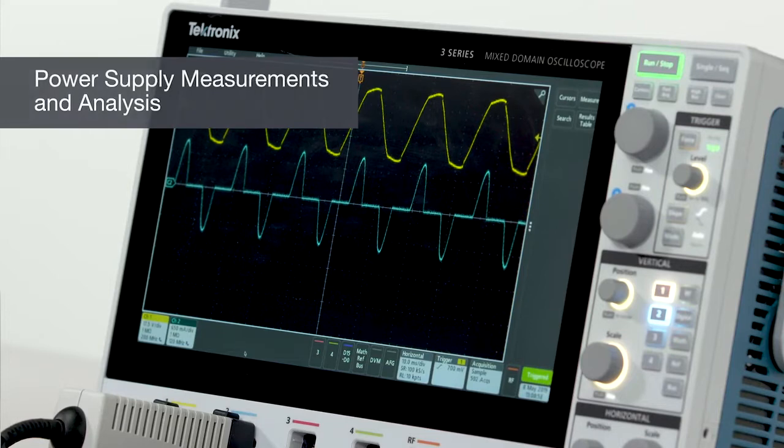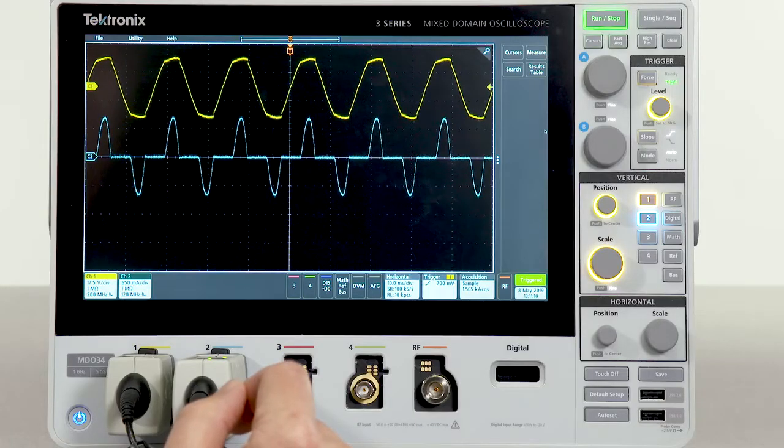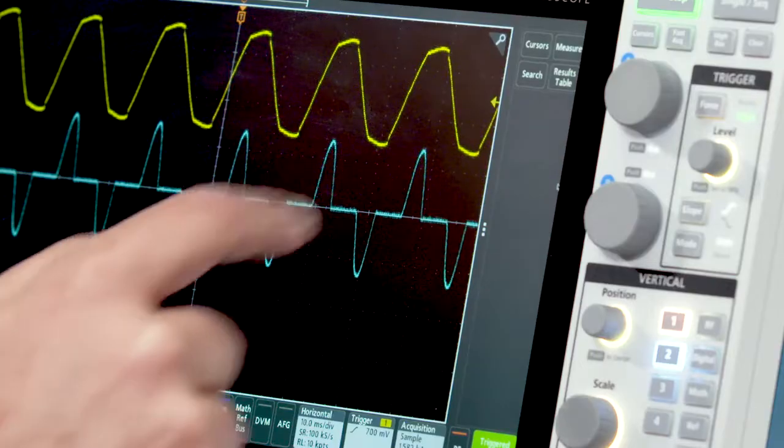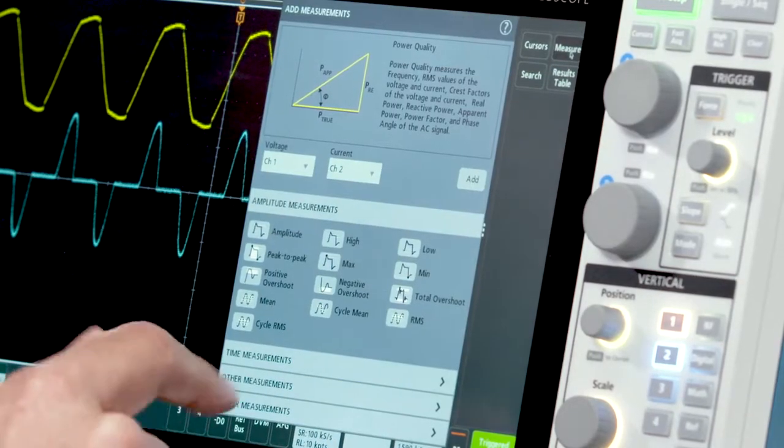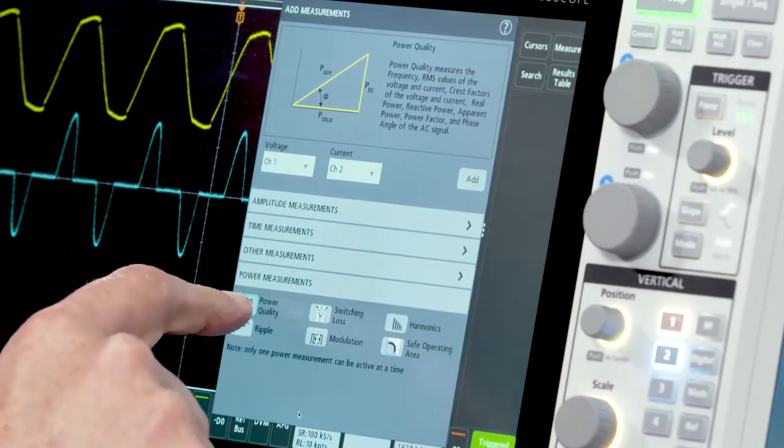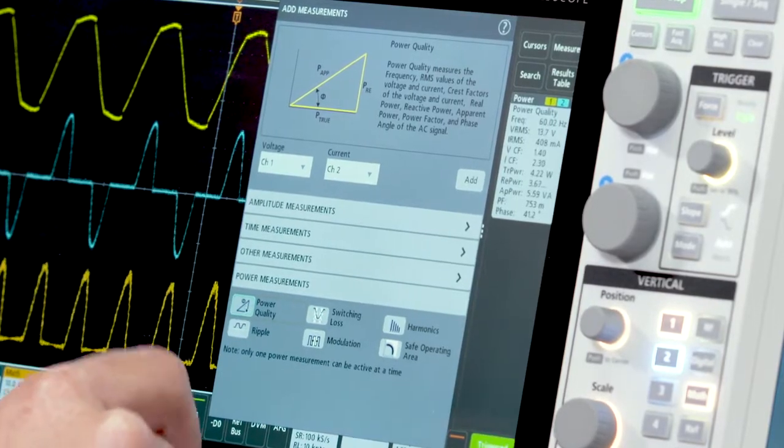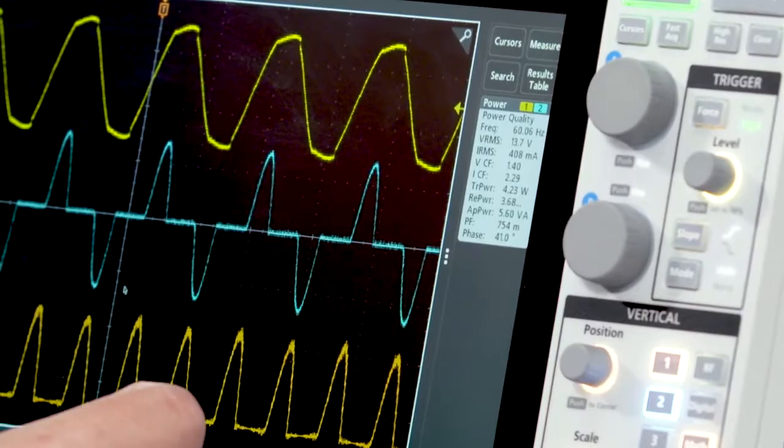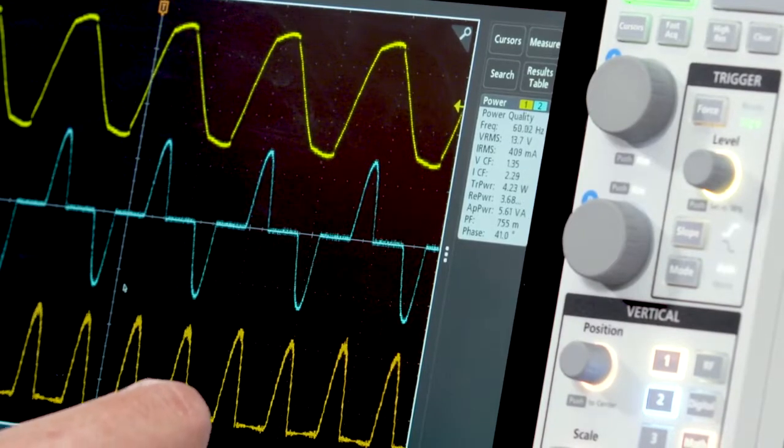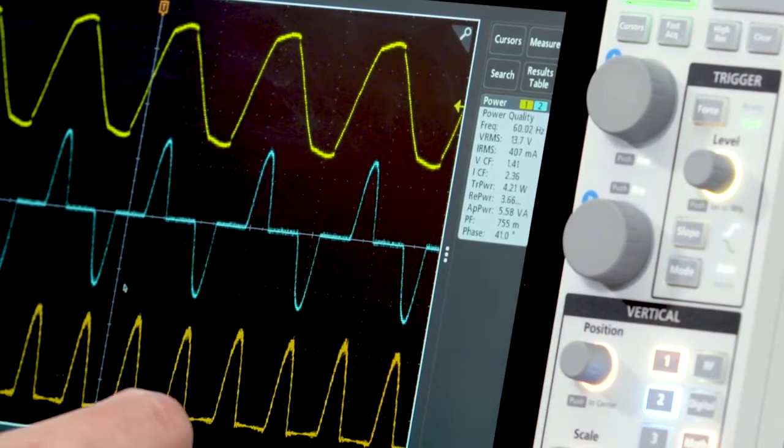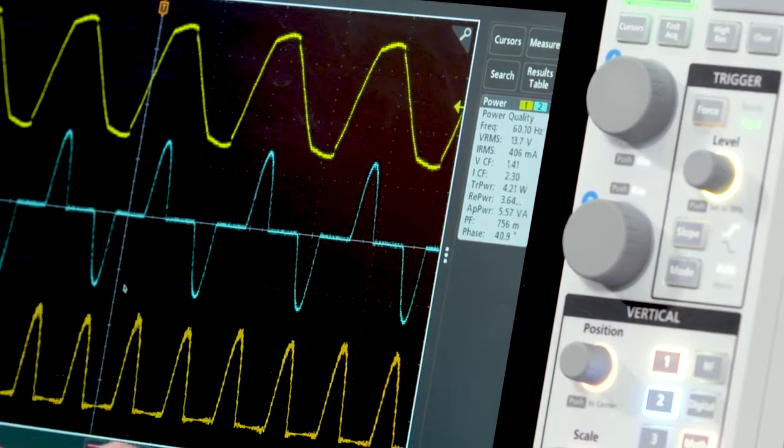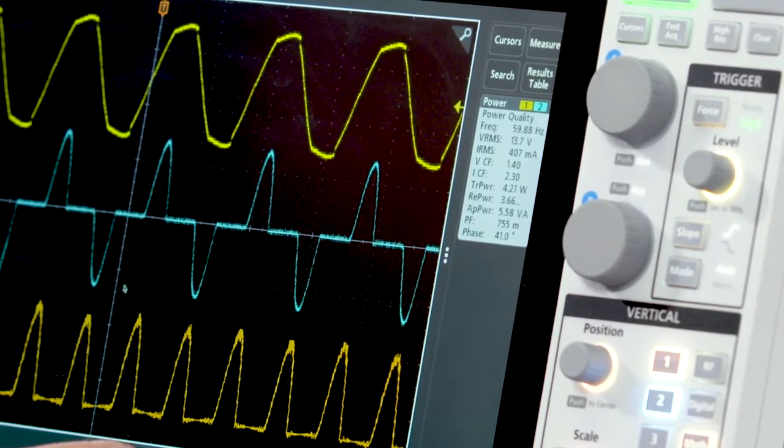With the optional power analysis package, it's easy to make end-to-end power supply measurements. Making power measurements is just as easy as regular measurements. To do so, go to the measure menu, select the power measurements panel, and in this case, we want to look at power quality. Once we've selected it, you'll see we get a new badge in the results bar indicating things like true power, reactive power, apparent power, and many other useful pieces of information.